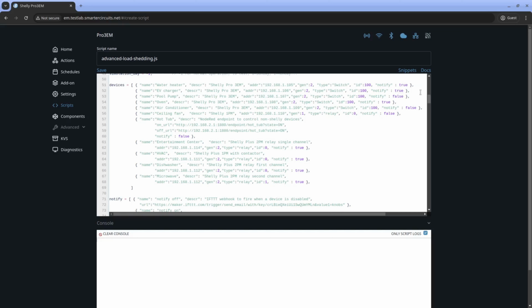That brings us to schedules. For schedules, you can specify a name, whether or not you want to use the schedule, a start time, what days the schedule applies to, a description, and a priority order for this time frame. You can also override minimum, maximum, polling time, cooldown time, and you can set a notification by name to be fired for on or off events.